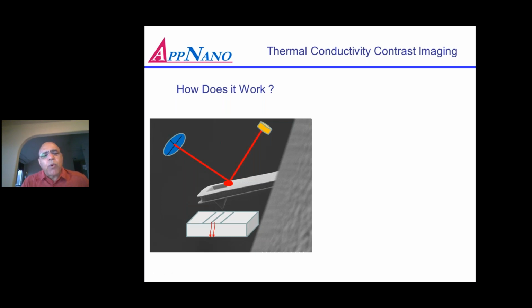So you have to have a compromise between the temperature change because of the heating and the sum signal you are getting. This is because we are splitting the laser into two halves. One is heating the thermocouple, and the other is giving the sum signal for the laser feedback. When you move the laser, in our module you can see the temperature change displayed directly. This heats the thermocouple, and you can see the temperature in the module. So you can optimize where the maximum temperature comes, and then you can start doing the experiments.